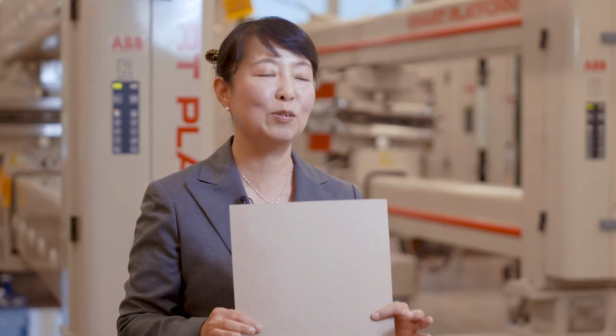So they need to set an expected deviation. The expected deviation is what's achievable and reasonable between the online sensor and the offline lab. That deviation usually comes from three areas: the online sensor accuracy itself, the process deviation, and the lab accuracy. All three of these areas contribute to what we call the error between the lab and the online sensor. So it's really critical to have a good sensor correlation strategy. This will help them achieve very accurate results.